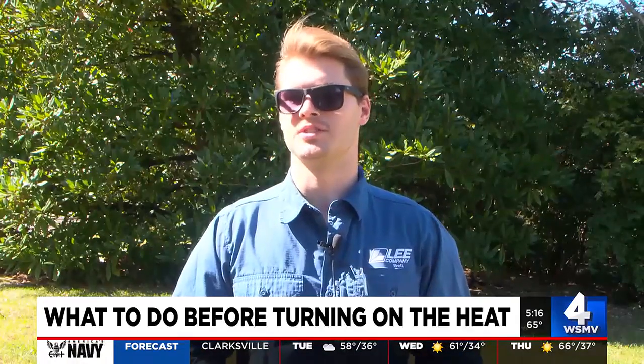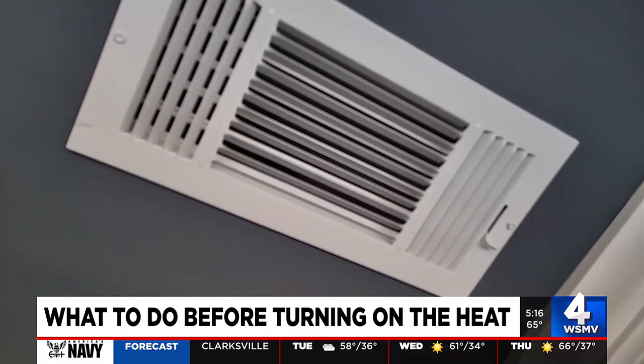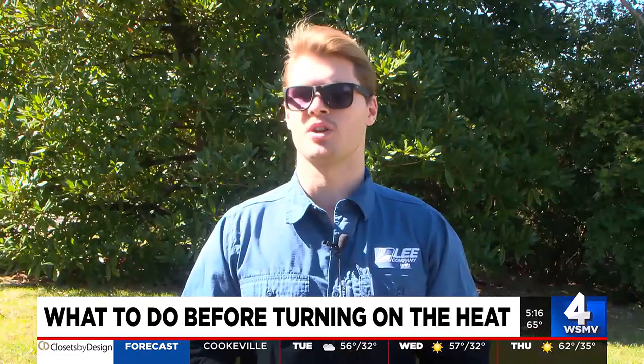As a customer, you can save money and not have us come out for just a little simple issue. Next are the air filters — these need to be changed every 60 to 90 days. A clogged filter will restrict airflow to the system, which can overheat the system long-term and can cause parts to go bad.